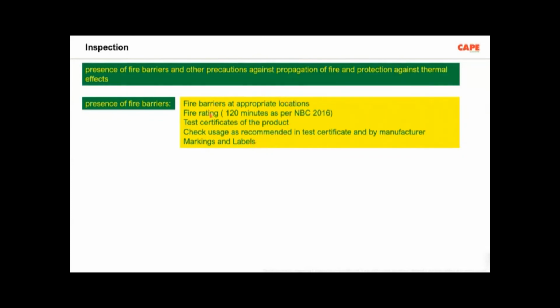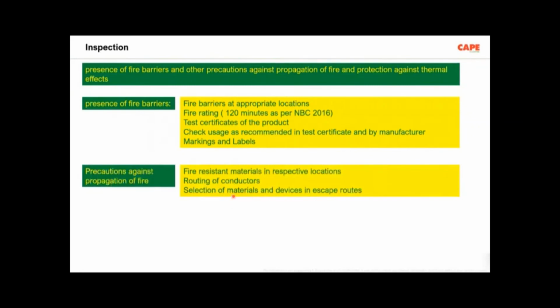So it is the job of the inspector to ensure that all these 5 points are inspected and that he is recording it in his report. As a result, 1 of the 3 requirements is handled. The second requirement is precautions against propagation of fire. How are you stopping the fire from propagating into critical areas? Here, for example, fire resistant materials in respective locations, routing of conductors, selection of materials and devices in escape routes. These also must be inspected.